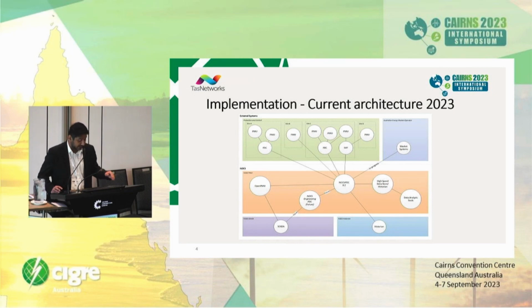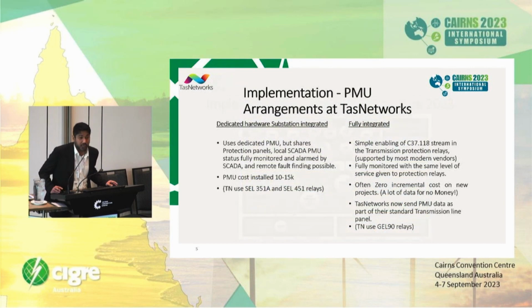We are also working on developing a link with the market in the future, but that's not done at the moment. Now there are multiple ways you can deploy PMUs. You can have a standalone system, which is what we have, and you can also have your protection relays enable C37.118 and utilize the PMU functionality in them. We are doing that as well. We are using SEL 351 and 451 relays. These are the relays, while the others are standalone PMU units.